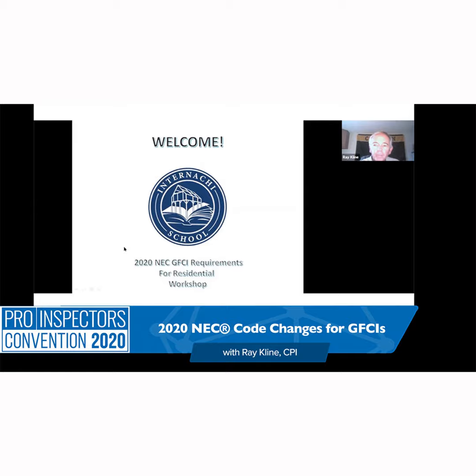That brings me back to nuisance trips too. I'd like to talk a little bit about that. You, or someone you know, may have a GFCI receptacle that trips often without much of a reason. Usually they don't trip for no reason at all. Either they're starting to malfunction and not working correctly, or you could perhaps have an old hand drill or an old vacuum cleaner that's got some current leakage in the windings of the motor. The GFCI can sense that, and it will trip.